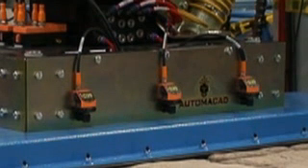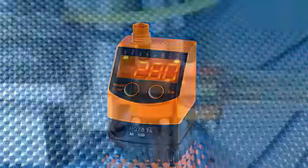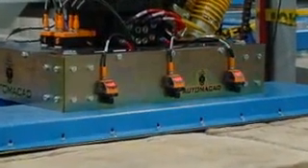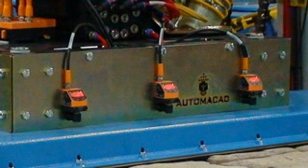Automacad consulted with their sensors and controls partner, IFM Efector North America, to find the proper solution. IFM suggested their PQ series vacuum sensors that are specifically designed for pneumatic applications and offer an extremely small footprint. The compact, cube-shaped sensors easily fit on the tool head and offer a bright four-digit numeric display. A push-button setup offers simple adjustment of set points. Each tool head is mounted with six PQ series vacuum sensors with a measuring range of negative 14.5 to 14.5 psi of full vacuum.